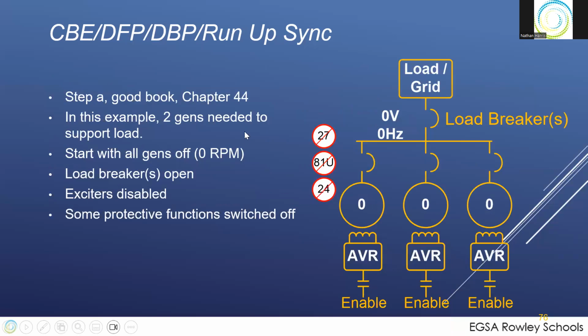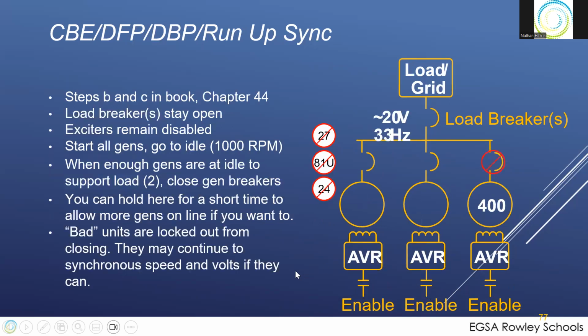So quickly, what it is: you start with some protections disabled, 27 undervoltage, 81 under frequency, 24 volts per hertz. You disable those protections. Your load breakers are open, your generator breakers are open, and the exciters are disabled. So you're ready to start in this condition. If you need to start at that point, you send a start signal, and the load breakers stay open. You send a start signal to all the generators.